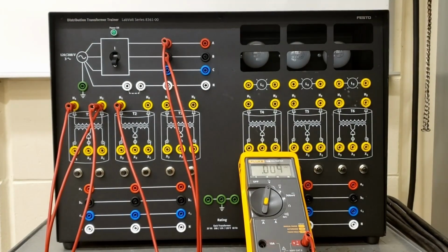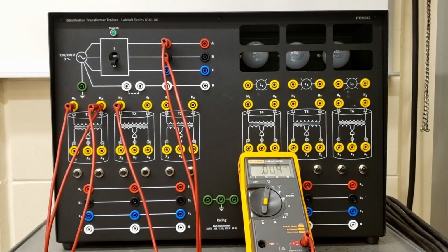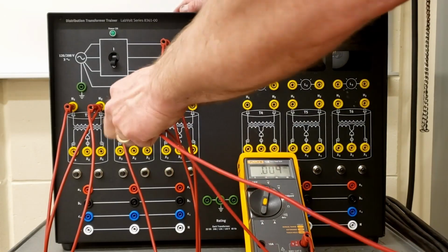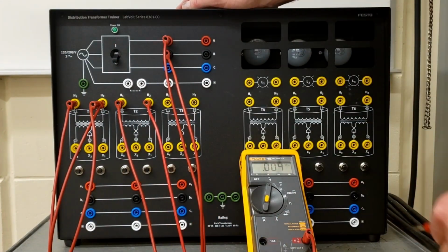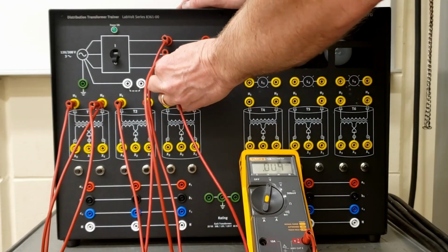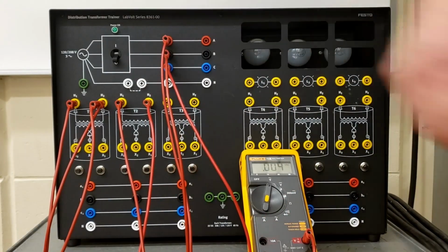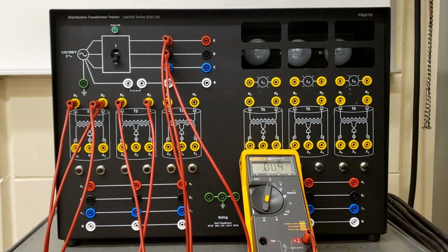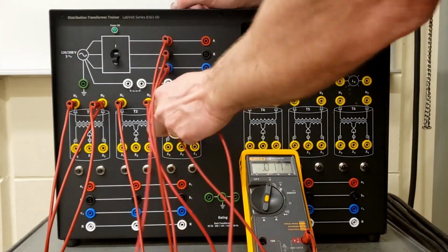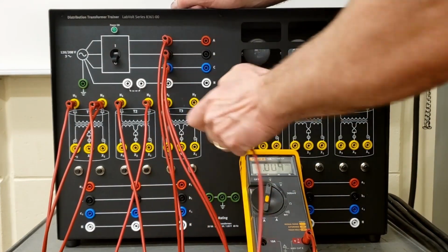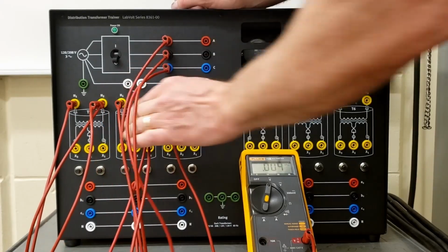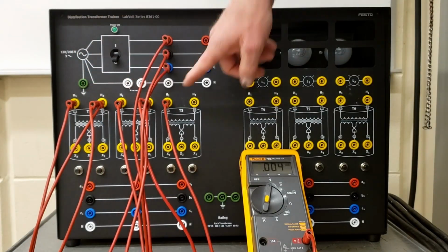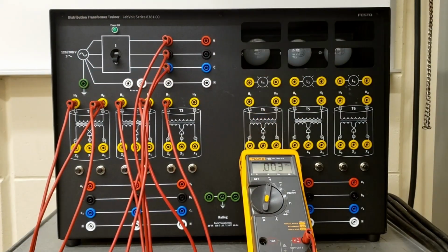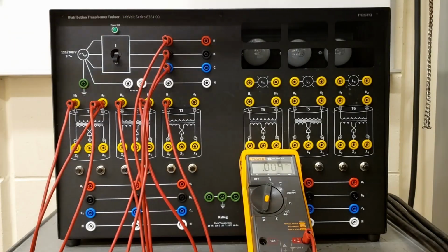Okay, so that's B. This one's got to go back to C. So this H2 of transformer 2 has to go to line 3. So that's B to C. We're going to jumper that one, so that H2 and the subsequent H1 of transformer 3 together there. So A to B, B to C, and H2's got to go back to A now.